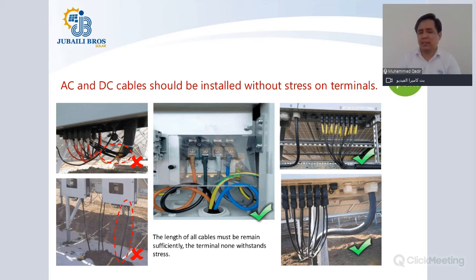Similarly, on the right side, the DC cables are connected very loose with curves, and there is no stress on the connection point to the solar inverter. So similarly, at the bottom right corner, you can see both the AC and DC cables are installed with a very loose connection, and thus no stress on the connection points. So please consider it when you are installing your HUAWEI solar inverters in the field.